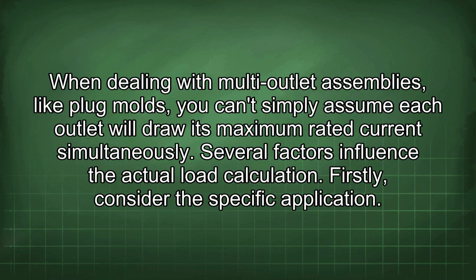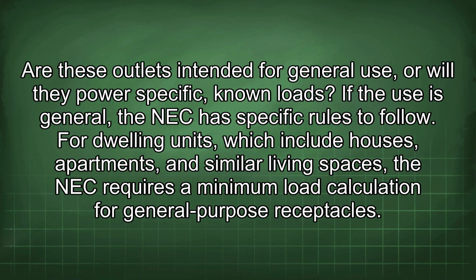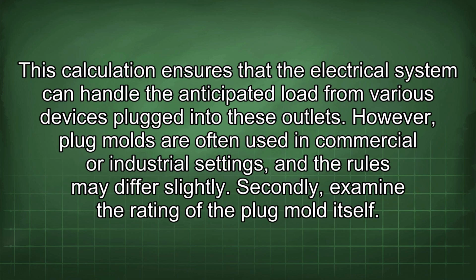Firstly, consider the specific application. Are these outlets intended for general use, or will they power specific, known loads? If the use is general, the NEC has specific rules to follow. For dwelling units, which include houses, apartments, and similar living spaces, the NEC requires a minimum load calculation for general-purpose receptacles. This calculation ensures that the electrical system can handle the anticipated load from various devices plugged into these outlets. However, plug molds are often used in commercial or industrial settings, and the rules may differ slightly.